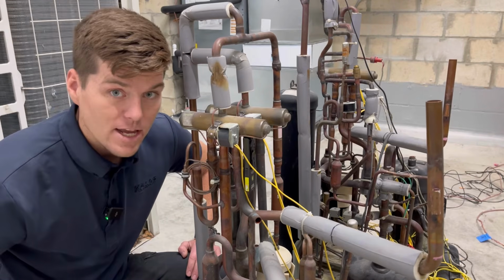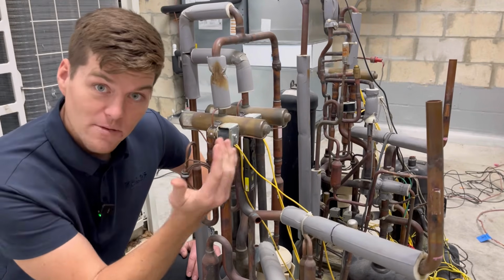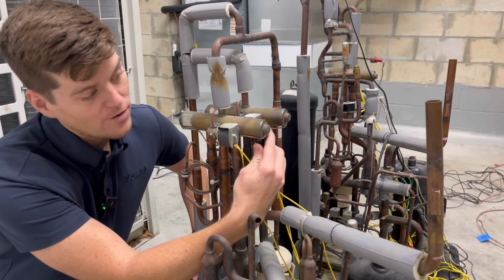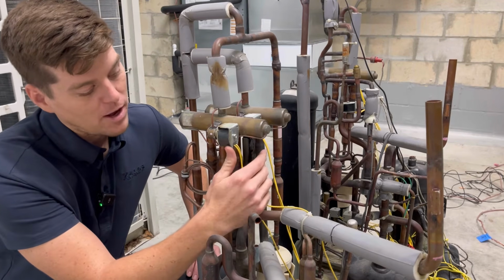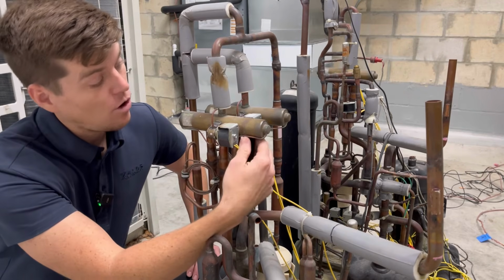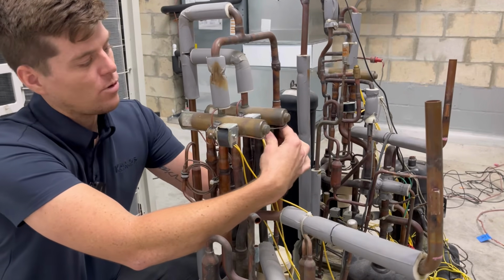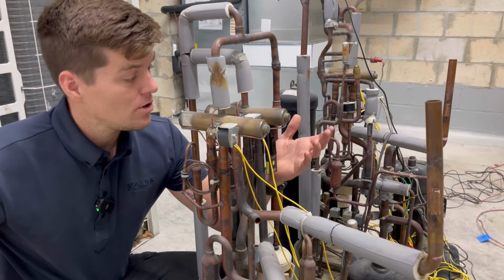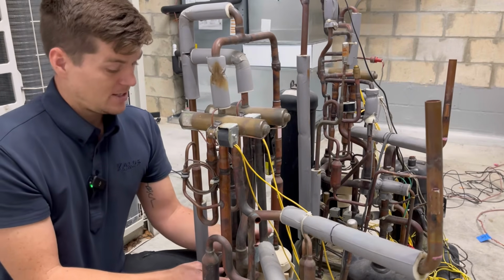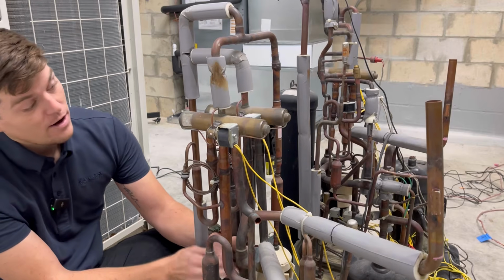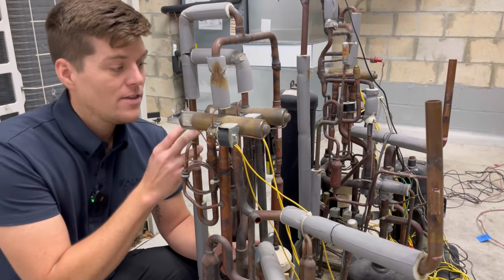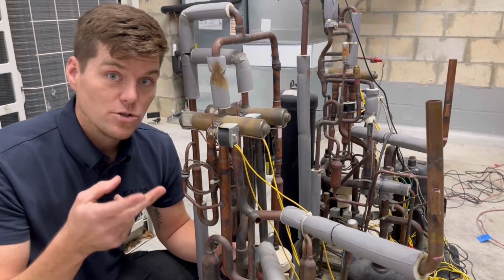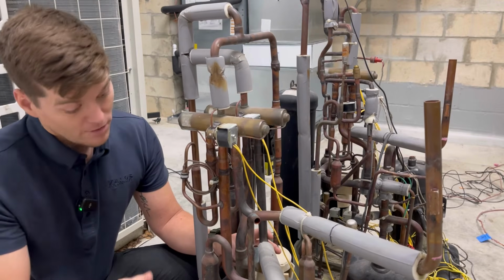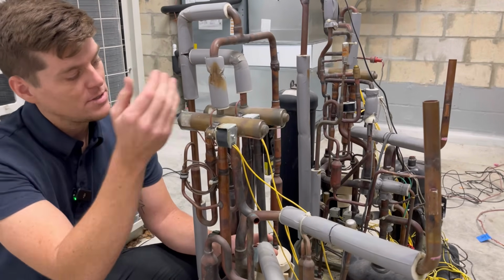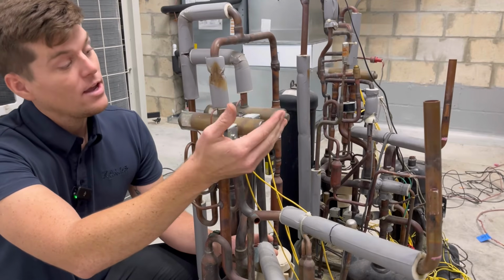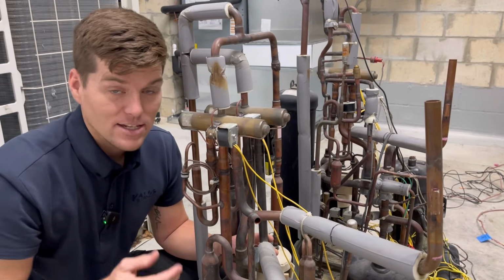Now, when I shift over to heating mode, this will shift. It will drag the magnet with it to the end of this valve here, and that'll tell me that the four-way valve for this module has shifted correctly. It's shifted all the way to the end. And the same thing is for the dual pressure line. You'll notice here that it's also all the way to the left here, which means that it's connecting my suction line over here, right? Hot gas is connected to my dual gas line. This is probably going to be energized in the cooling state where it's dual suctions, where it's connecting my third line over to my suction line, which means that this should be shifted all the way to the right-hand side, not the left-hand side like it is now.